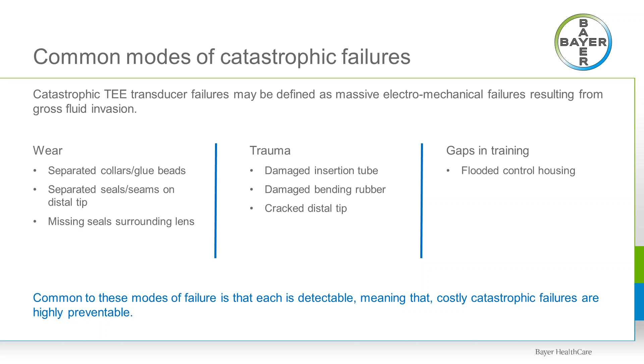Knowing that catastrophic failures are preventable, let's look at some of the root cause analysis of each of these types of classifications. Like I mentioned, wear and tear is always going to be present. Your tires are always going to wear on your car. You always have to change your brakes. Same thing is true on a TEE probe. Your bending rubber is always going to wear. The seams on your collars, on your bending rubber are going to separate over time. The seals are going to degrade on not only TEE probes but standard probes as well. So gross fluid invasion as a result of missing seals or separated materials is really a direct result of a gap in some kind of periodic inspection.